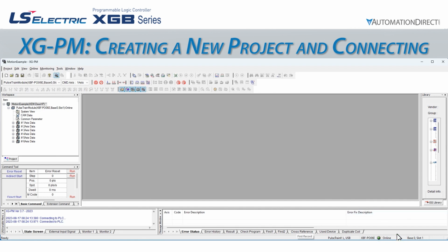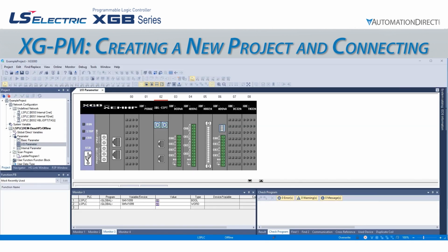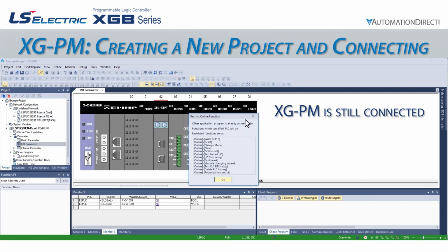It is important to note that we are able to use the same USB cable and connection to be online with both the CPU for programming in XG5000 as well as the motion controller in XGPM. When using XG5000 and XGPM at the same time, we need to connect the XG5000 software first. If we connect to XGPM first and then connect with USB from the XG5000, we will see this error message appear. At this point, the software has now disabled these online functions.